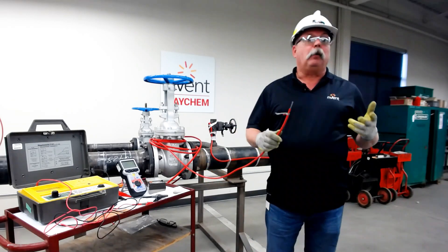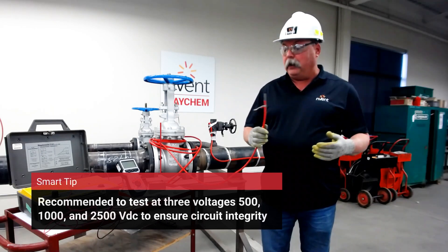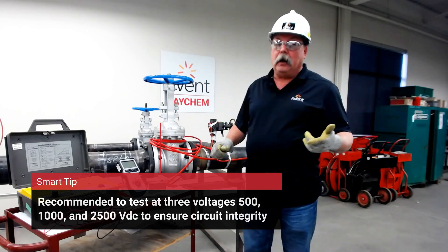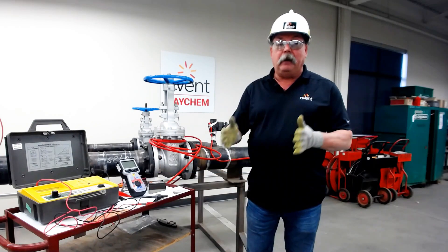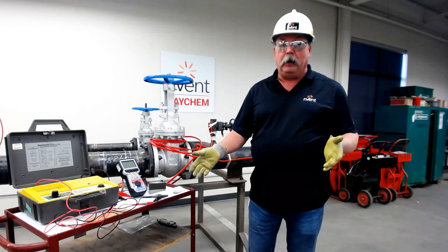Raychem specs require testing at three voltages: 500, 1000, and 2500. Now 500 and 1000 always get done, but the 2500 one gets missed quite a bit, and a lot of cables pass at 1000 but they'll fail at 2500.